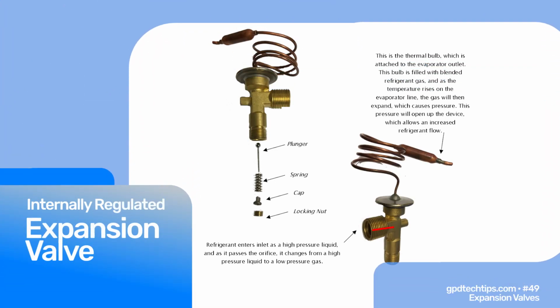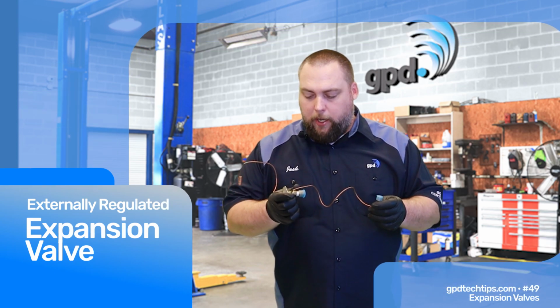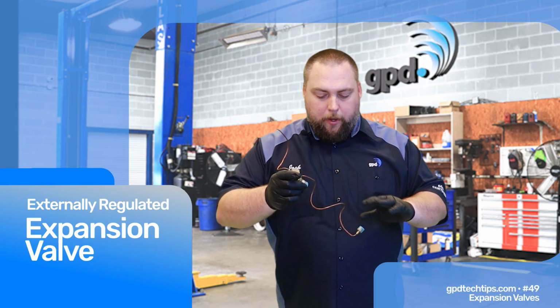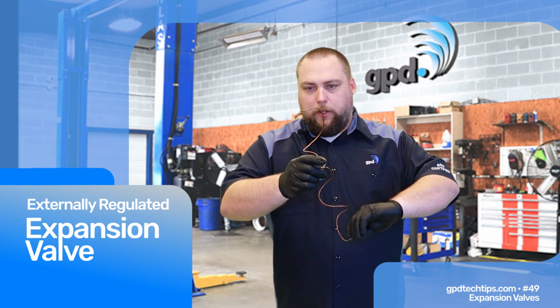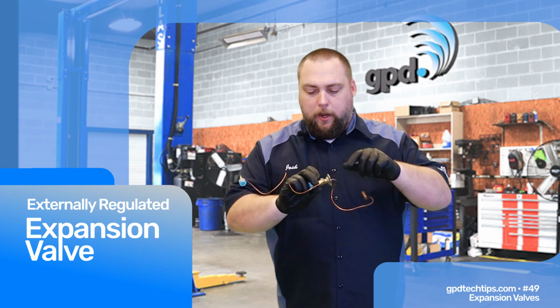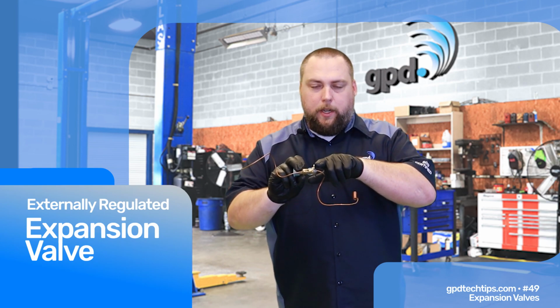On an internal regulated expansion valve, what you have is a spring inside of here that is putting some counter pressure on this diaphragm on the inside, and there's actually a little bit of refrigerant inside of this tube. So what happens when that refrigerant heats up, it's going to put pressure on the tube here, and it's going to change the position of this diaphragm to change the flow rate. Now this one is actually an externally regulated expansion valve. It actually uses pressure from the other line to regulate the pressure here, so we're actually working against each other a little bit here to change the flow rate.